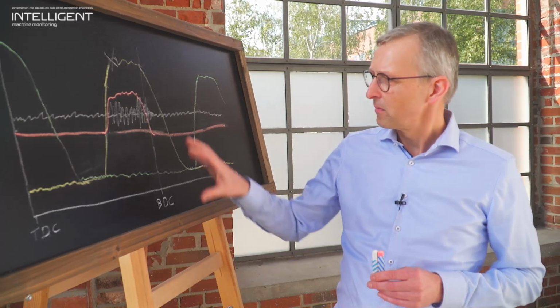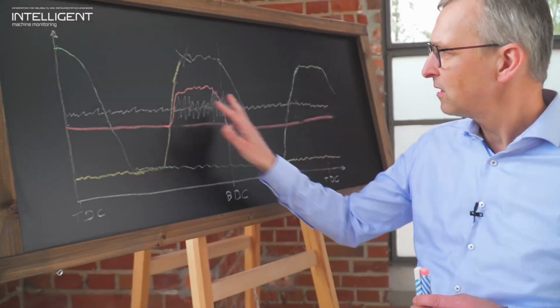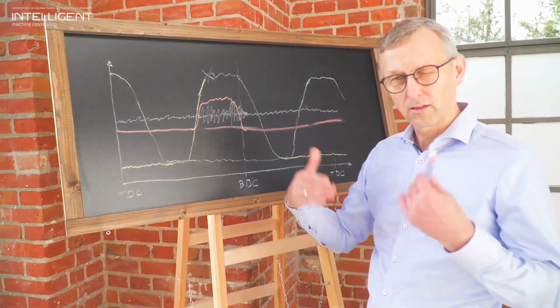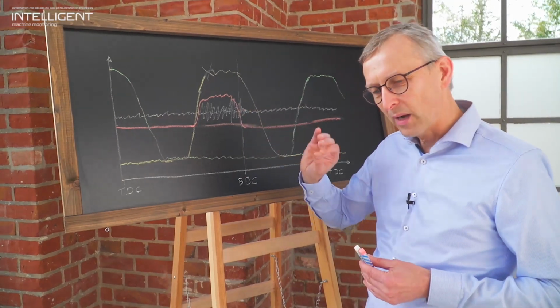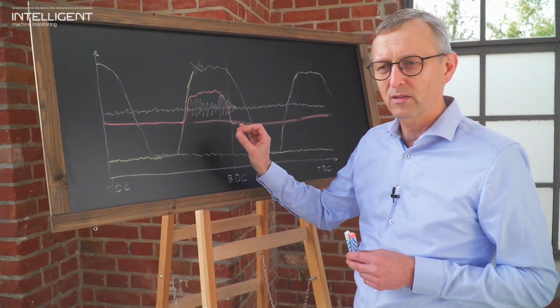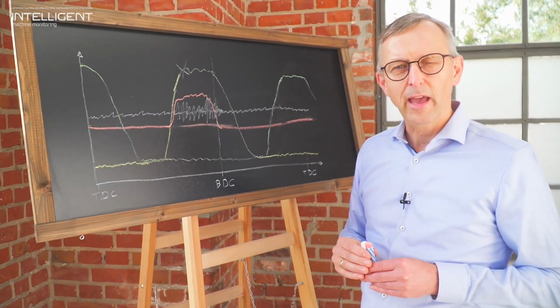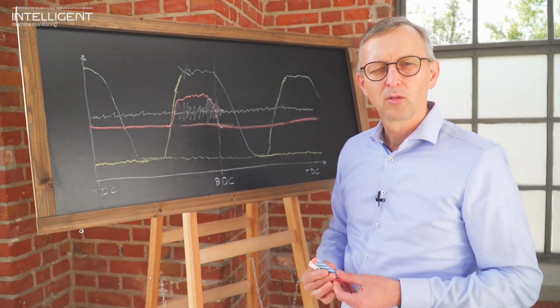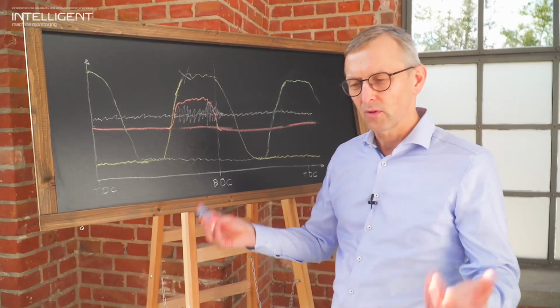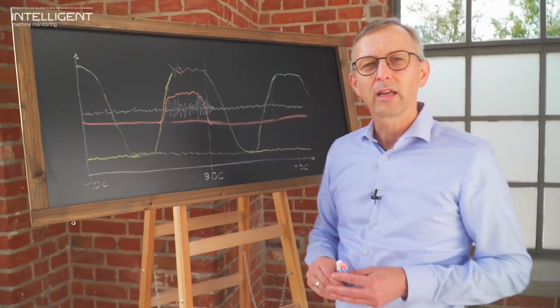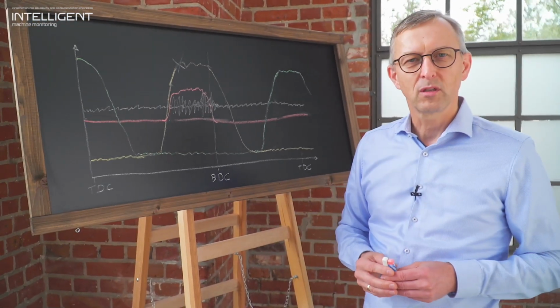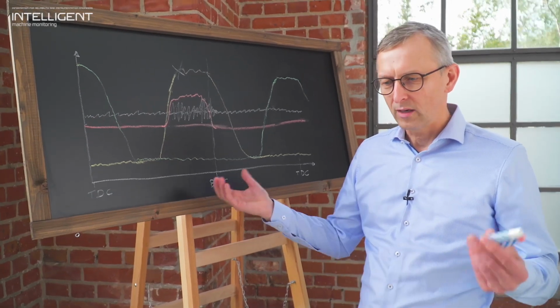So modern systems can detect these kind of things inside such a machine at an early stage. So when we are passing small portions of liquids, there can be action taken to look into our piping or in our pulsation damper to find if there are high volumes of liquids there, and then releasing these liquids more frequently in the operation, and this will then save the machine to really see such a dangerous liquid slug.